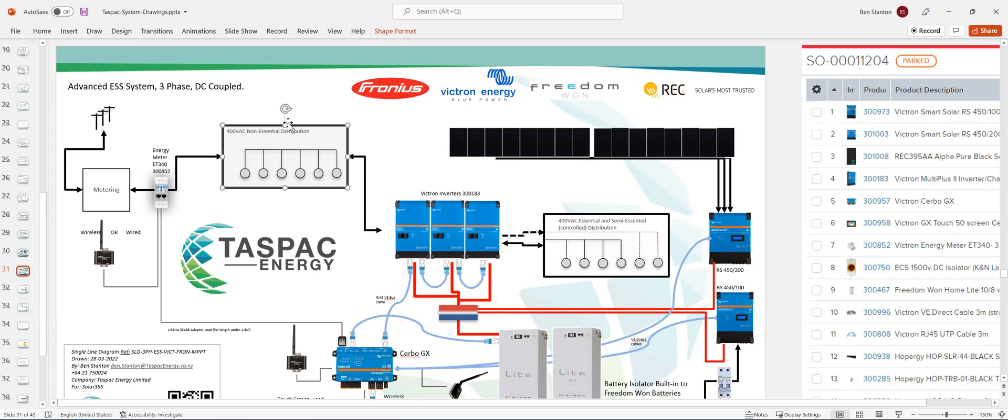But when the grid is there and you're running from the inverters, the essential is alive. So you can either have two completely separate boards, but generally what happens is you just split one row or even one RCBO or one RCD or a set of circuits as non-essential.